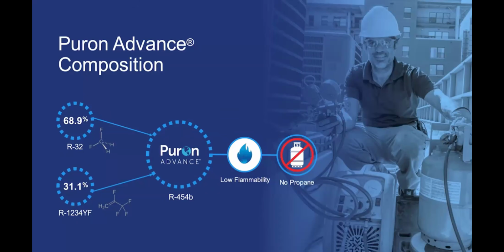As mentioned, 410A is 50% R32 and 50% R125. R32 is the flammable one. This is the one that's causing all these refrigerants to be flammable, but it's in 410A, and that's not considered flammable. That's because R125 is basically a flame suppressant. So flammable thing and flame suppressant mixed together means non-flammable thing. In the case of R454B, we also have R32, which is flammable, right? We have 69% of that, but then we have 31% R1234YF, and that is also flammable. So two flammable things mixed together continues to be a flammable thing.